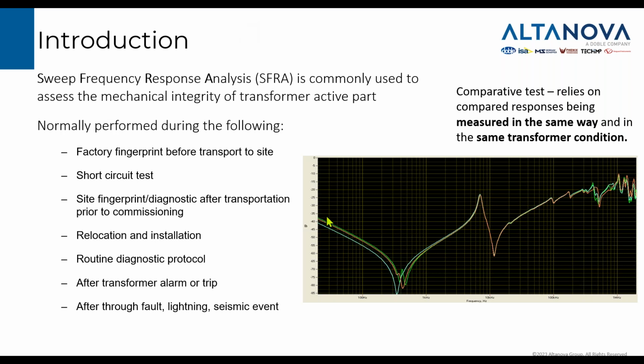You can see 3 lines which go along the frequency range, and they have some damping parameters at different frequencies showing the response of the winding. That response is equivalent to the RLC network made by the winding, and therefore it is also a response of the geometry of the winding. So if something happens to the transformer and the windings get deformed, these responses are expected to change their shape as well. So this is a comparative test. We always have to compare it with something. We can only tell the transformer is good if the trace is good. I will describe that further in detail in a minute.